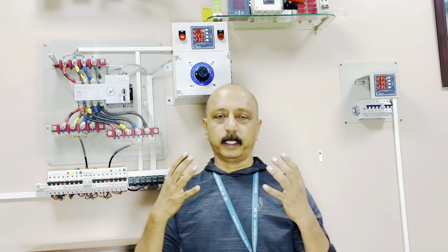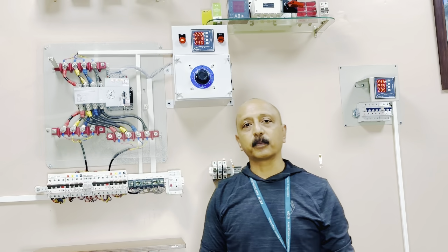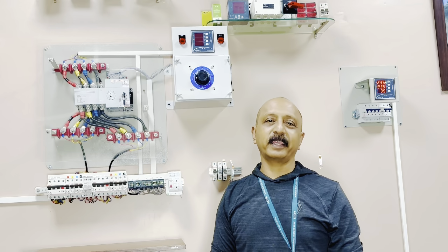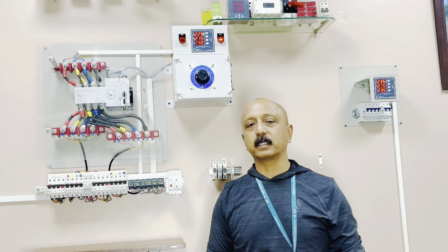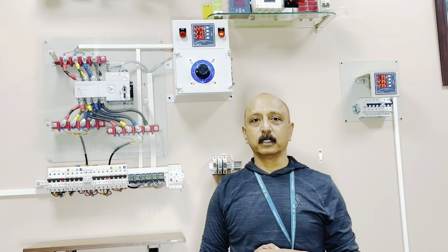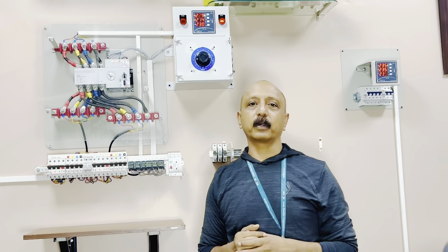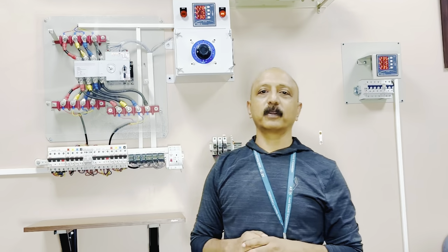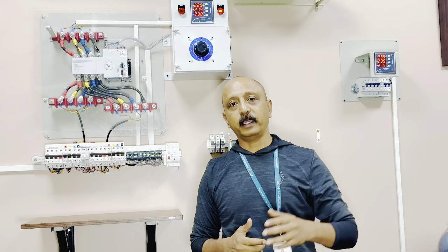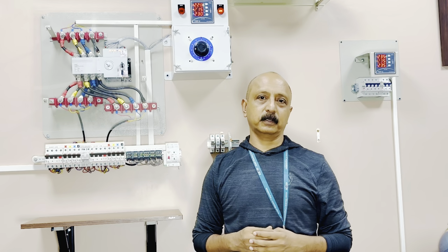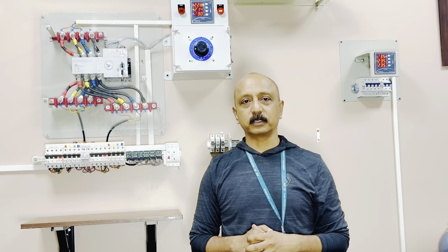The whole ATS is tested and programmed to operate at about 310 volts. Every three-phase device is actually tested at 310 volts. So in the event of, let's assume, a neutral failure elsewhere, if the line voltages go high, it can, to some extent, handle that kind of situation.